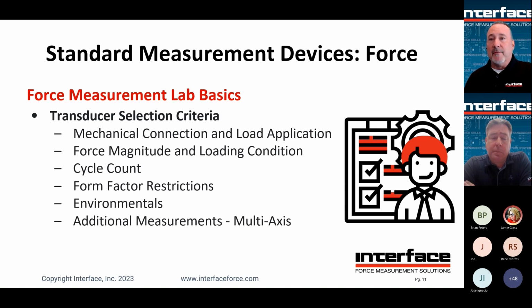Cycle count: are you doing fatigue tests? Are they very high cycle count? You want to make sure that you're selecting the correct standard for that. Make sure it's fatigue rated if you're doing fatigue testing. Maybe your test stand is just pulling samples occasionally and only doing very low cycle counts, so you don't need fatigue rated. Form factor restrictions: do you have space constraints in your test stand? Do you need small compact size, or do you have room for larger sensors? Maybe you're doing compression only load, so you could fit a much smaller load cell in, with lower height restrictions.